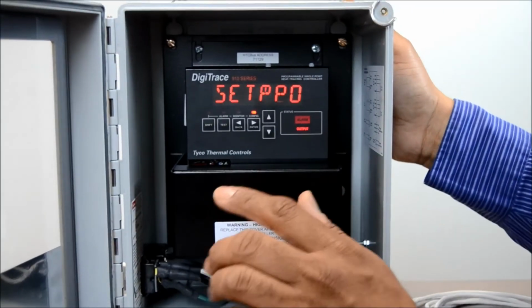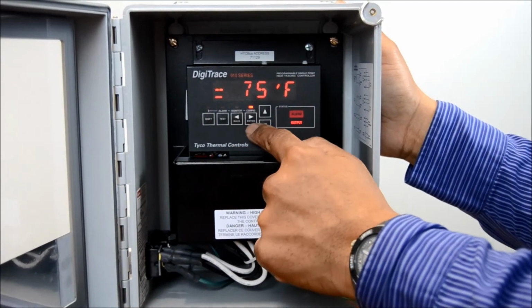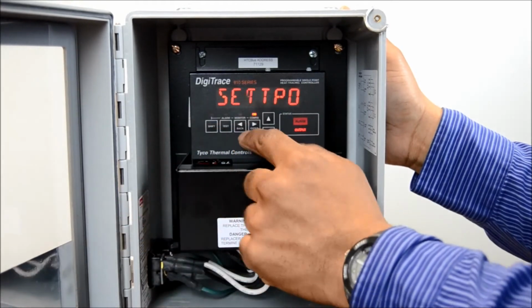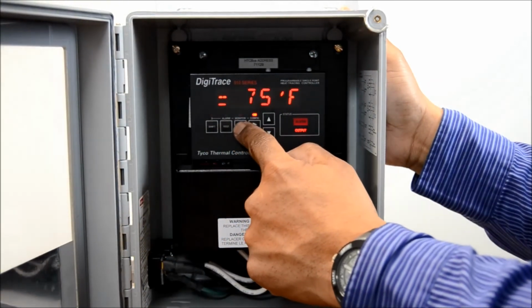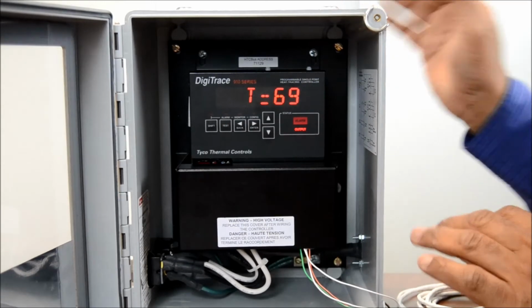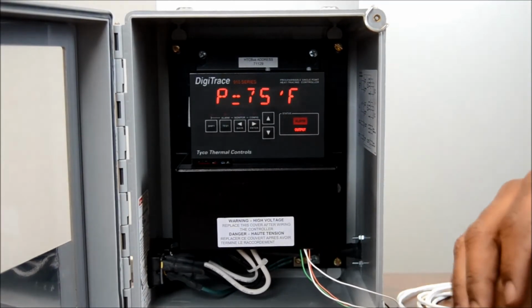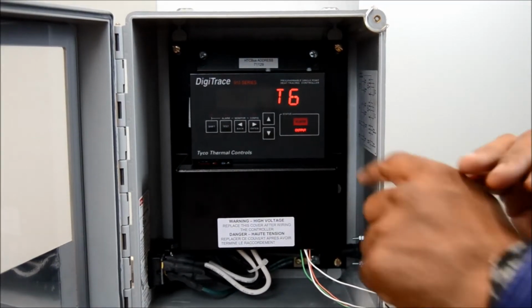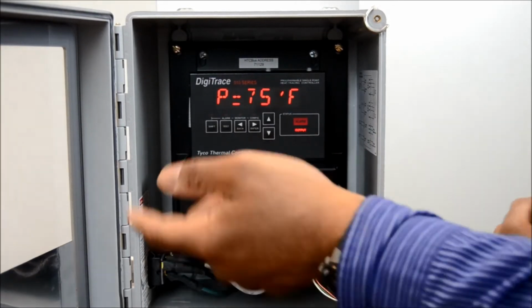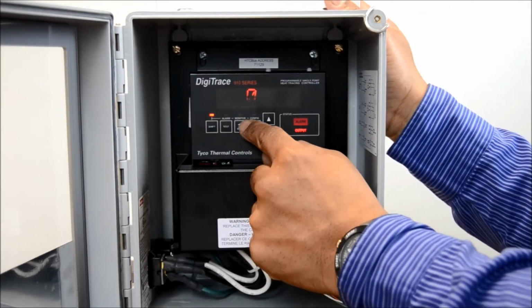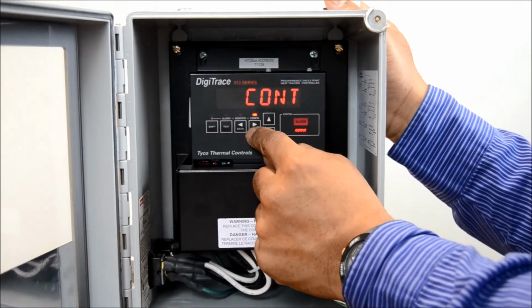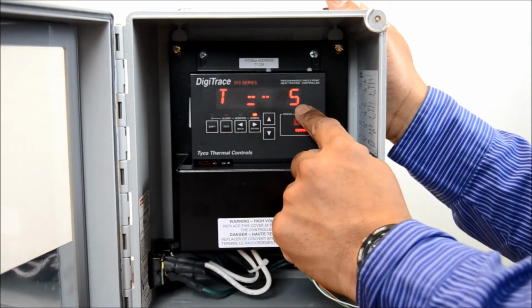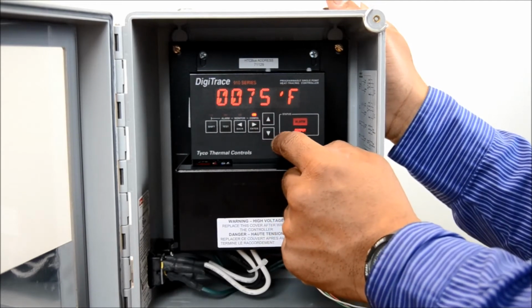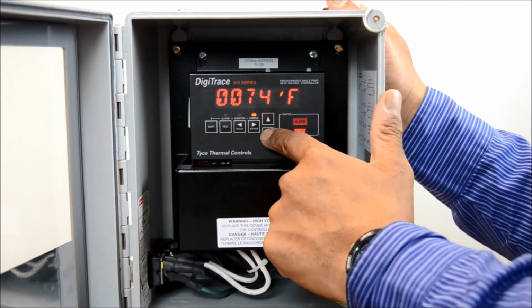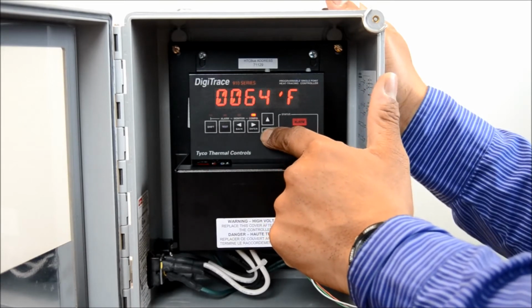Now, as we come back to the controller, we can back out of this menu if we want to keep the set point at the same set point, and you do that by hitting the back button. And now you're out of the system and the heat trace is on and it's working correctly. The output light is on. Now let's lower this. You go to Shift, Configure, once again, temperature set point. You're going to hit Enter again. It's blinking, so I'm going to go all the way down to 51 degrees again.